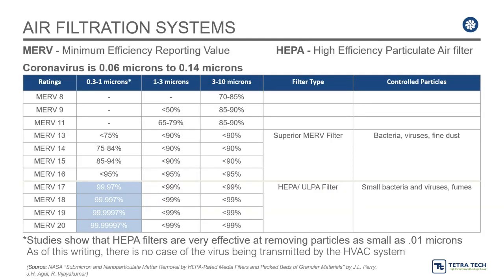You can see by this chart that the lower level filters are not very effective in the 1 to 3 micron size, but when you get to MERV 13 up through MERV 15, these filters are very efficient and effective, and are recommended.